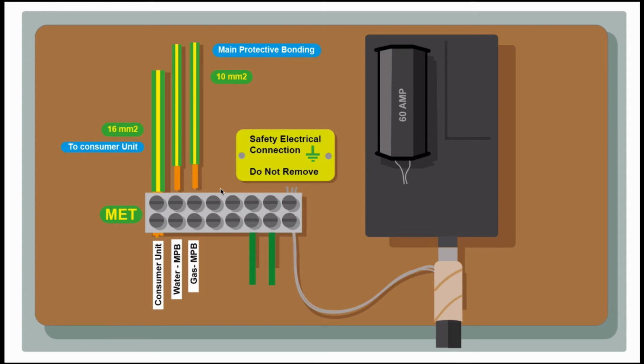Right, we've got our new main earthing terminal. I've removed the nut and bolt type, and I was only happy to do that because I knew I had a nice flexible earthing connection. The earthing conductor was nice and long and it wouldn't be putting any strain on the soldering joint, and it's got its fabric wrap as well, so that's well protected. So I was happy to swap that out. I've replaced the old bonding, what I presume is the bonding, and so with that, those earthing connections are still in place. I haven't installed the main protective bonding yet because we're not sure what's happening with the gas and plumbing, but I've replaced the conductor going to the consumer unit with a 16mm squared green and yellow conductor.